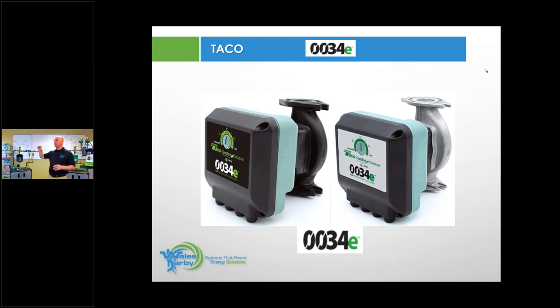So if we have a dual aquastat where we got 160, 180, usually the 160, the low side is geared around hot water. So the low side is geared around the bottom end of hot water. The high side is geared around satisfying your home in heating mode. So the circulator will do its thing. It doesn't know what the temperature is. It just wants to maintain a 20 degree delta T.